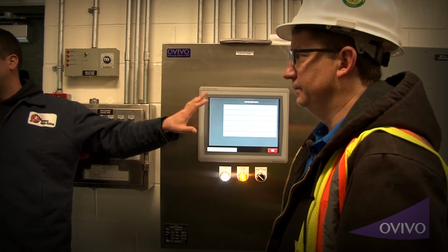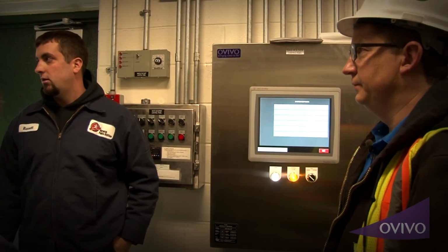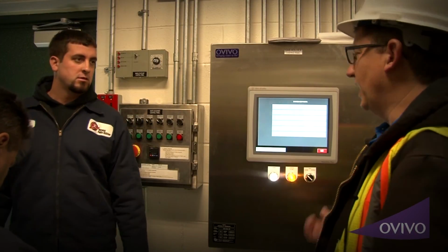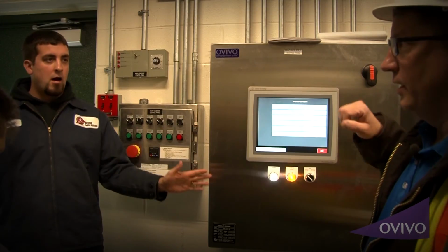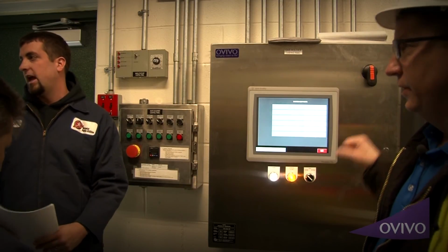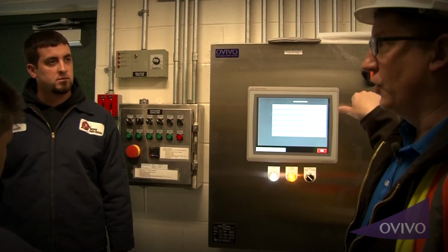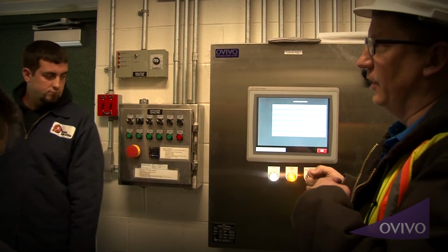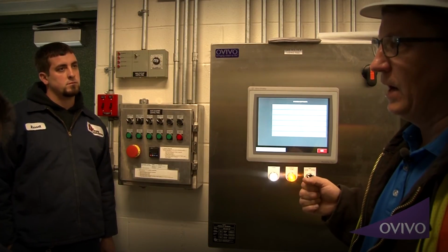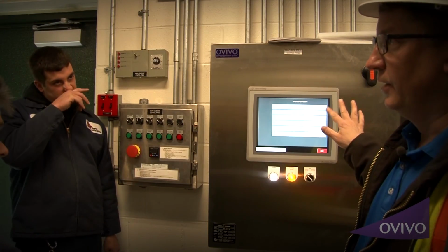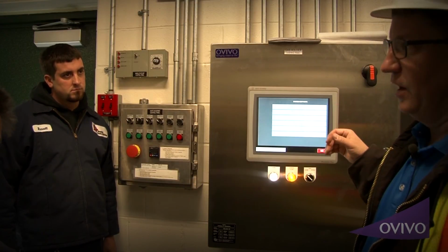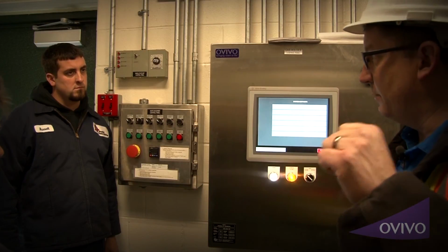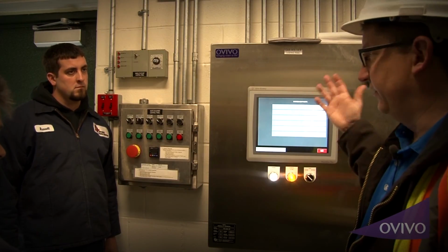It was off, with only the UPS running the computer, not running the blower. When I opened the door, it killed all the power to it. The second I closed the door, the UPS took over and ran the actual controller until I clicked it back on. But that only takes care of this. It doesn't take care of the fans. There's no battery backup for the fans. It's just going to monitor. If we had a power outage right now, it's not going to operate the fans. The purge mode can trigger straight to open if you had to manually push it, but other than that, this thing is just monitoring.